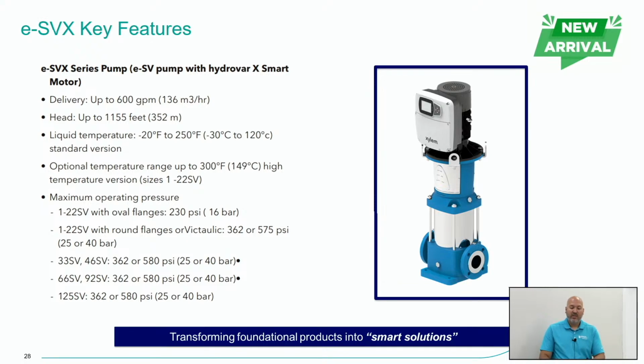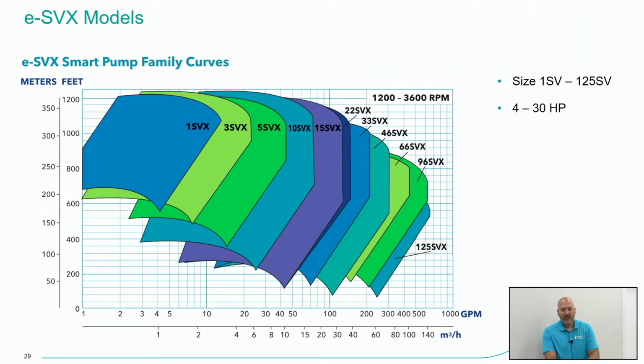But the ESVX then would give you flow rates up to 600 GPM and head up to 1,100 feet of capability there. A lot of the other key features as far as the liquid temperature, maximum pressures and things you can use is going to be the same as the ESV that you're using today. Like I said, the only cutoff is going up to the 30 horsepower range. So here are the family curves. You can utilize this still on the 1 SV all the way to 125 SV, but up to 30 horsepower. And these are the family curves giving you an idea of the flow and head capabilities of each specific range within the ESV family.